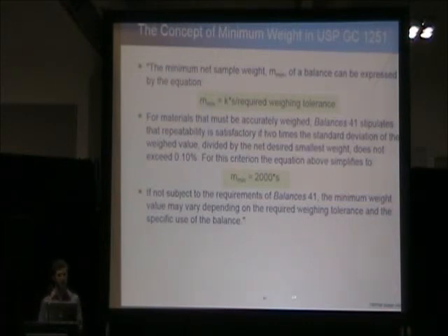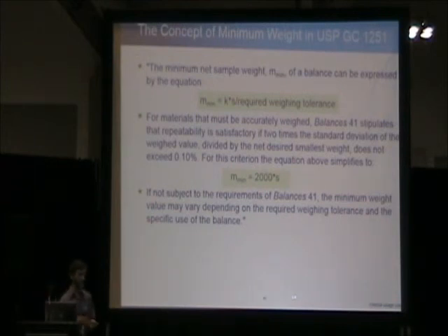Now, just for purpose of this conversation, USP is the only regulatory compliance agency that actually has a specified process tolerance, which is 0.10%. Even ISO doesn't state a particular weighing tolerance for your applications. All your weighing tolerances should be established by the end user based, again, off of risk analysis of your particular application.